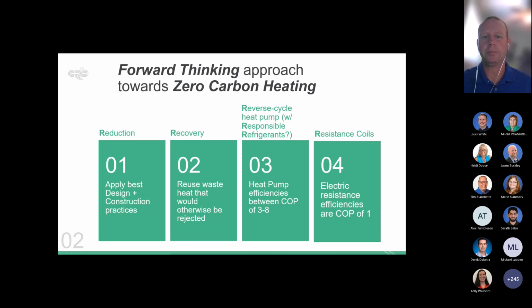That's ideal, but there are challenges with ammonia toxicity, hydrocarbon flammability, and CO2 pressures. So there's not really a perfect solution on the natural refrigerant front, but we are seeing some very low GWP alternatives, some of those HFOs that have come out recently. And again, the last step is to use electric resistance only for the things you absolutely have to - that's step 4.